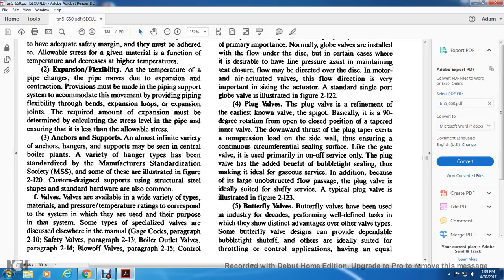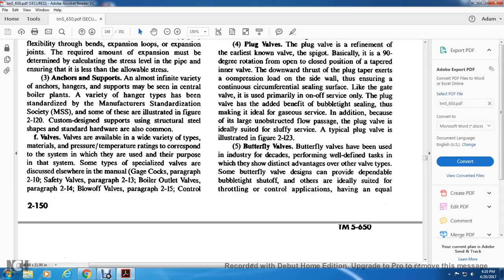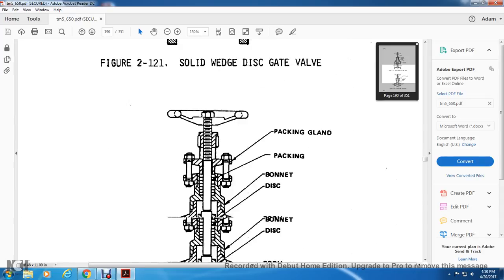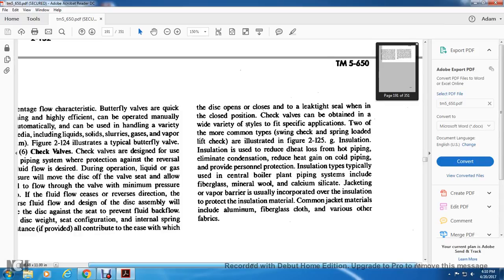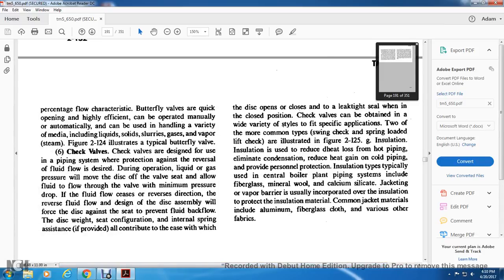Butterfly valves have been used in industry for decades, performing well-defined tasks in which they have distinct advantages over other valve types. Some butterfly designs provide dependable, bubble-tight shut-off, and are ideally suited for throttling control applications having equal percentage flow characteristics. Butterflies open quickly, are highly efficient, can be operated manually or automatically, and can handle a variety of media, including liquids, solids, slurries, gases, and vapors. Figure 2-124 illustrates a typical butterfly valve.